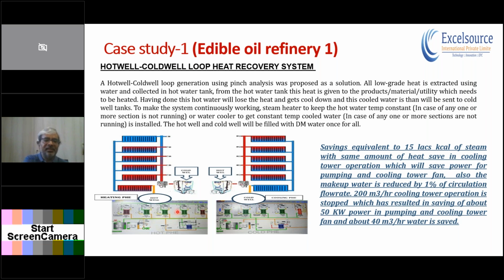downstream, where the cursor is, you can see it is the PLC logic or the SCADA display. It may not be visible clearly, but these are all the heat exchangers installed, with a flow meter, temperature control valve and temperature transmitters. This tank is a cold well, installed with level transmitters. This is a hot well, again installed with level transmitters. We see that the water is circulated in a way that we don't end up adding any fresh water. This system is filled with DM water and circulated through the hot and cold circuit. It is a one-time filling of water into the system, and then it keeps recirculating throughout its life cycle.